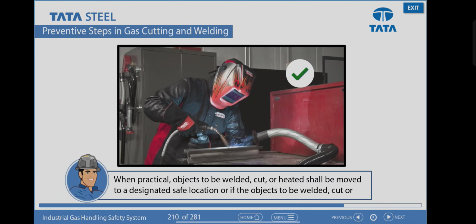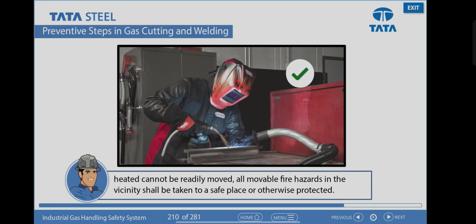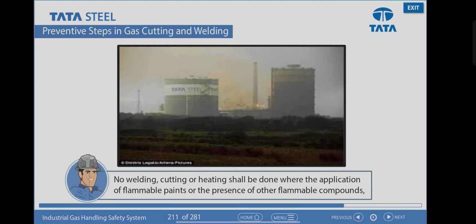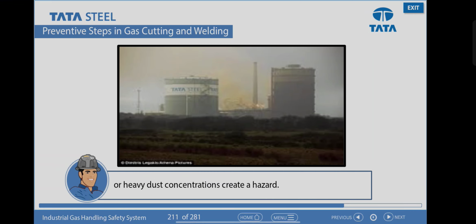When practical, objects to be welded, cut or heated shall be moved to a designated safe location, or if the objects cannot be readily moved, all movable fire hazards in the vicinity shall be taken to a safe place or otherwise protected. No welding, cutting or heating shall be done where the application of flammable paints or the presence of other flammable compounds or heavy dust concentrations create a hazard.